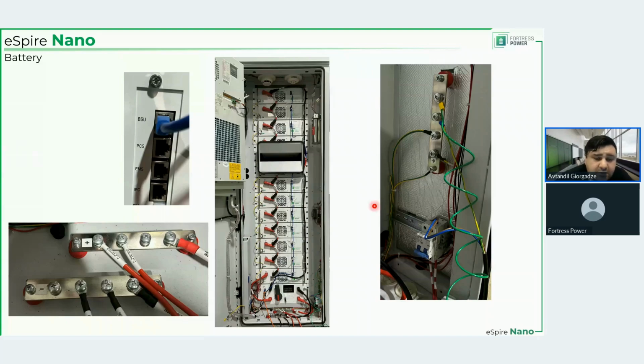Also, I'm going to get into the details of that, but this breaker is used only in the applications where the inverter is working with and is outputting 480 volts. For 208, the method is slightly different, and you don't use this breaker at all. But the ground bar, obviously, is used in both cases. So this ground bar has the internal grounds connected to it, so the shell of the batteries and the cabinet of the battery, and then this ground bar is connected to the inverter.